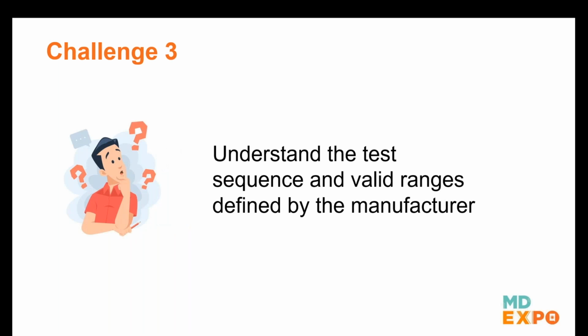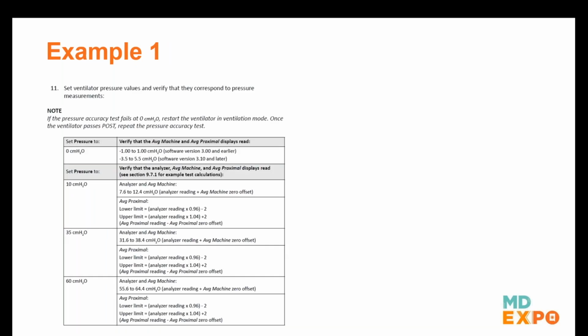Okay, so we just have 5 minutes left. The last challenge we're going to go through quickly is that sometimes we see that the sequence and valid ranges defined by the ventilator manufacturers are quite challenging to understand and to follow. So we have two examples for you. It's not expected that you can read everything here, but this is a very typical application where we have to calibrate different pressure levels. And sometimes it's as easy as it says, okay, set the pressure to 10 on the ventilator and your analyzer should read 9.5 to 10.5 or something like that. In this case, it's very complicated.